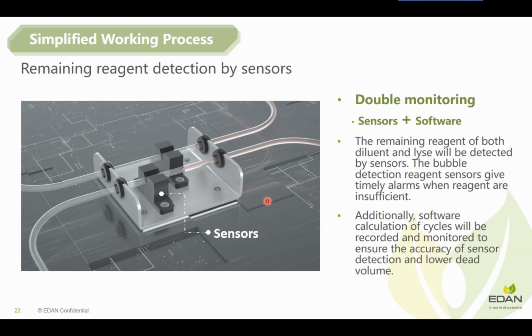Another practical improvement on H30 Pro is the remaining reagent detection. We use double monitoring, sensors and software, to detect the remaining reagent of all the routine reagents. When there are continuous big bubbles, it's the signal of reagent empty. Then sensors will give a timely alarm. Simultaneously, software is counting the cycles, so the reagent consumption will be recorded. By the double monitoring, the remaining reagent is well detected.